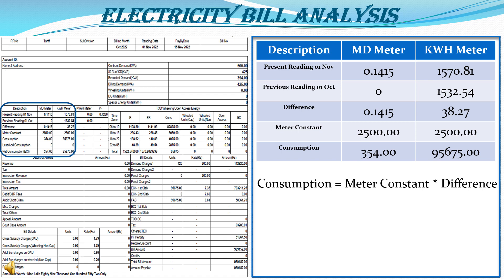How is consumption of maximum demand and KWH calculated? The difference is multiplied by the meter constant to get the consumption total. Multiplying 2500 by the maximum demand difference of 0.1415, we get a consumption of 354 KVA as mentioned in the electricity bill. And multiplying the 2500 meter constant by the KWH difference of 38.27, we get the KWH in units — 95,675 units — which is the net consumption to be charged in the electricity bill.